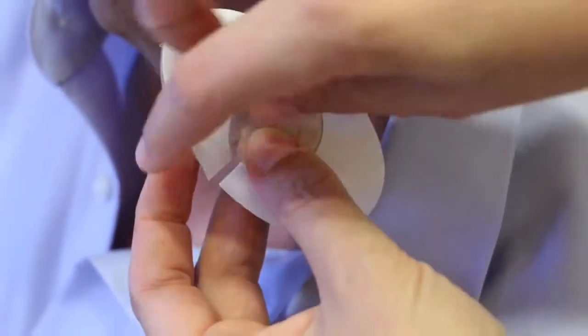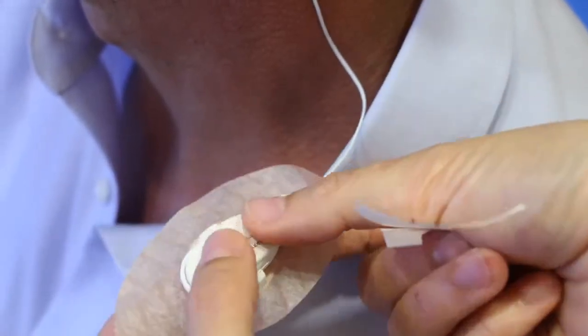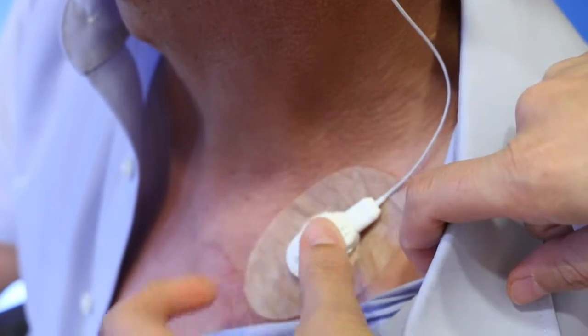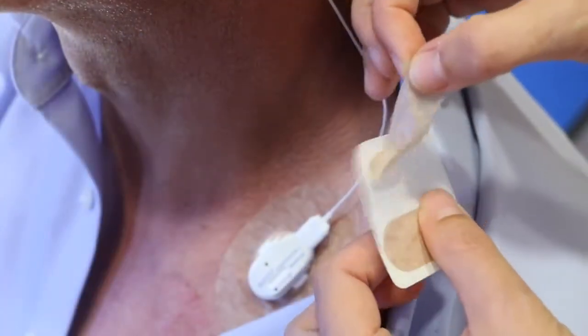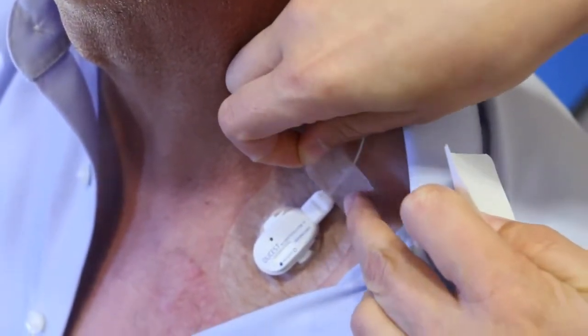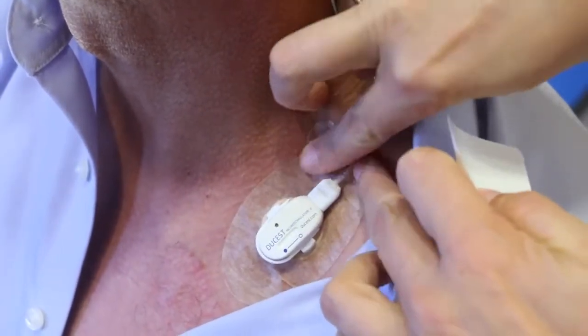The strength of the electric current is set slightly — the patient should not feel it too strong. Many patients cannot feel the pulses after a while, and this is okay. Important: too strong a current density is counterproductive and could cause pain during the therapy. We recommend an additional placement of a plaster at the begin of the cable.